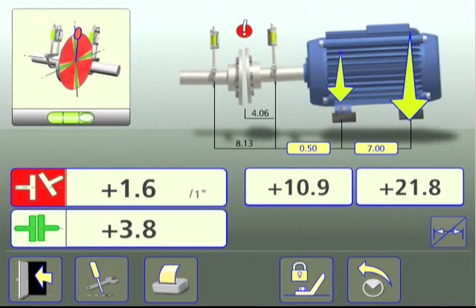The XA offers a solution to base-bound or bolt-bound machines with its feet-lock function. Feet-lock allows the user to select which feet to lock and which feet will be adjustable.